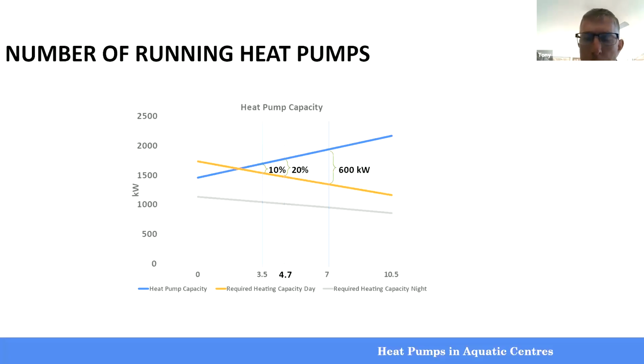But the main point to discuss with the consultant at the time was that he wanted to put in some extra heat pump capacity so that he had an additional 600 kilowatts in case he needed to reheat one of the pools, particularly the main pool, if it was shut down for some time or needed to be refilled with water, and they wanted to get it heated quickly. He wanted an extra 600 kilowatts of capacity. And this curve just shows you that you only have to get beyond 7 degrees in the ambient temperature, and you've got sufficient capacity there to do that.